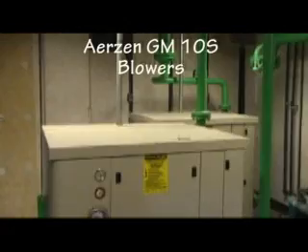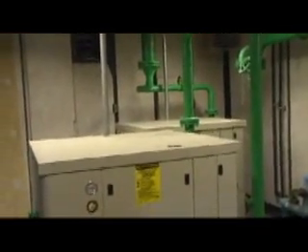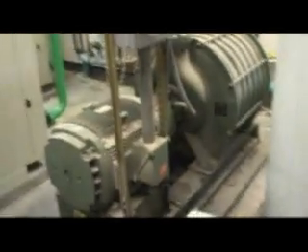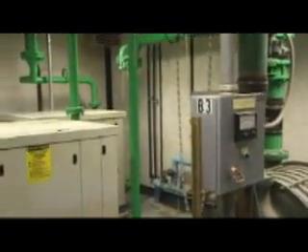It was tight in here because there were three centrifugals before, so we had to make it work. We wanted to keep the 60 horsepower for a backup, so we cut the other two out — there were two more beside it. The two that you have right now, they're handling the load. Are they both running to handle the load? Yes. And this 60 HP is sort of a common spare at this point — it's like twice the flow of both of those.